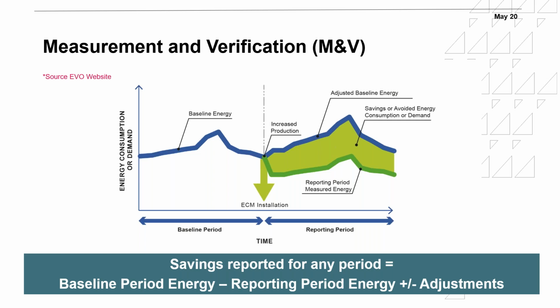Anything that is different between what was happening during 2018 and what is happening in 2019, in terms of maybe occupancy got a little bit higher, or maybe occupancy got lower due to COVID-19, as an example. If you're doing an energy efficiency project on a hotel, the occupancy is much lower. We have savings, yes, but that's not due to the energy conservation measures alone. They are also due to the lower occupancy. So we need to go back to the baseline and adjust it to say, what if the occupancy of the hotel was only 50%? What would have been the baseline in that case? And we adjust the baseline, and now we compare our reporting period consumption to the adjusted baseline. This minus that will give us the reported savings. So the savings reported for any period is the baseline period energy, which is normally higher than the reporting period because we're trying to save energy, minus the reporting period energy, plus or minus any adjustments.